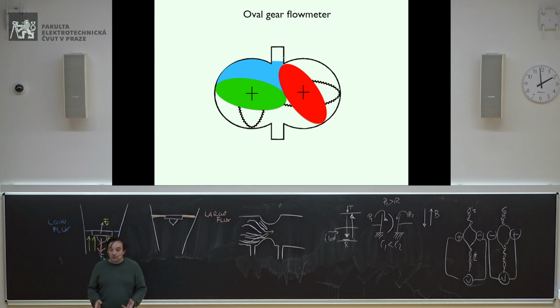So if the flow meter doesn't rotate, there is no way that you can have some flow of water going to the other side. Does it have an inertia? Absolutely. You have some mechanical parts, you have some gears, and definitely they have an inertia. If you don't have pressure enough to give the force to these gears to rotate, well, they don't rotate. But, contrary to the turbine, for instance, if they don't rotate, there is also no stream of water.